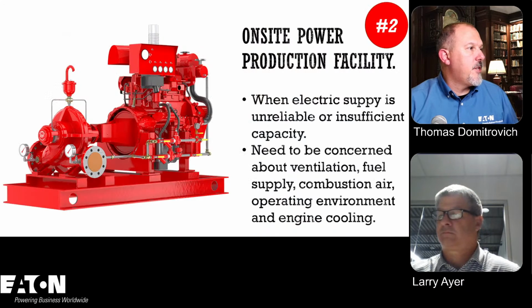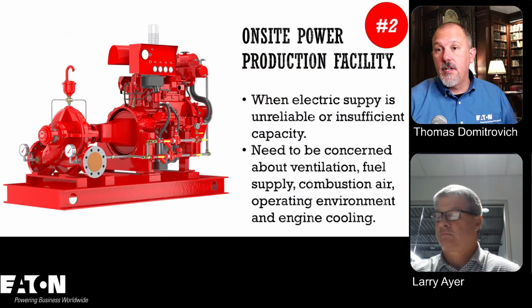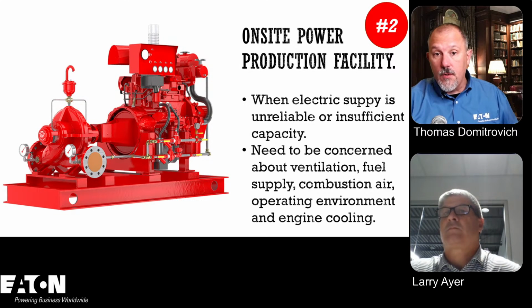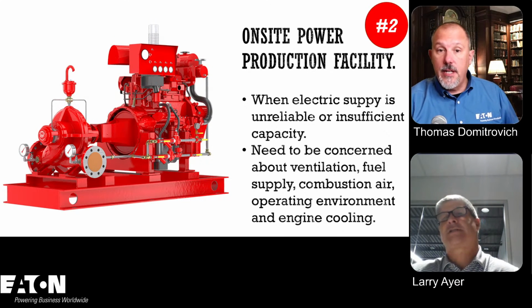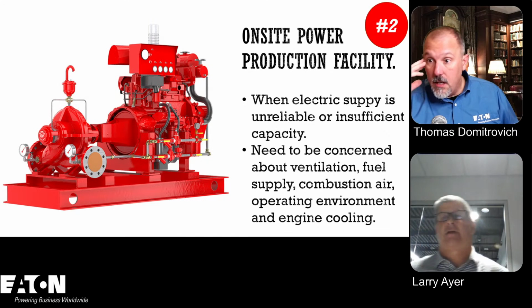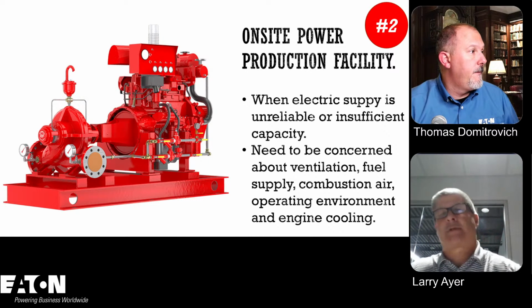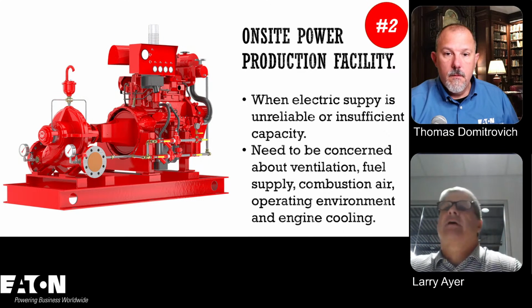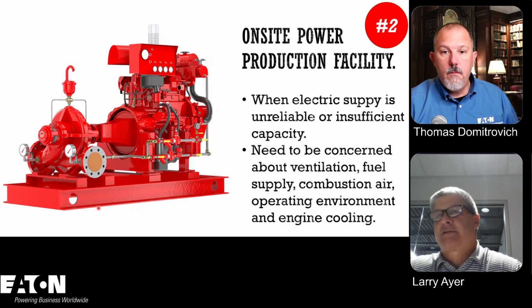And then you've got option number 2, which is your on-site power production facility. And that's all self-contained, right? So that's all listed together. The fire pump controller is on there. The diesel generator is on there. The engine is on there, the diesel engine that's turning. And you can see on there the water pipe connections on the bottom left of that pump. And so that is self-contained, and it's considered reliable.